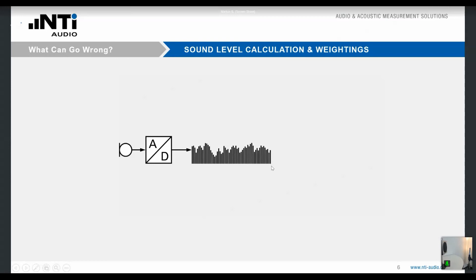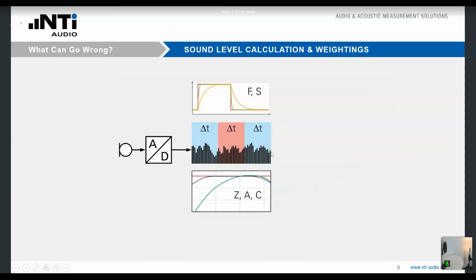This raw data will not be saved on the SD card. This wouldn't be feasible just for the sake of data volume. But this raw data plays a very important role because based on it, the instrument calculates the time weighting, the fast and slow weighting, the frequency weighting, Z, A, or C weighting, and it also allows the instrument to chop these samples into time slots depending on the settings from the customer. If you need a 100 millisecond log interval, the analyzer can do so by applying this time chopping on this raw data. So all these calculations are done on the instrument.